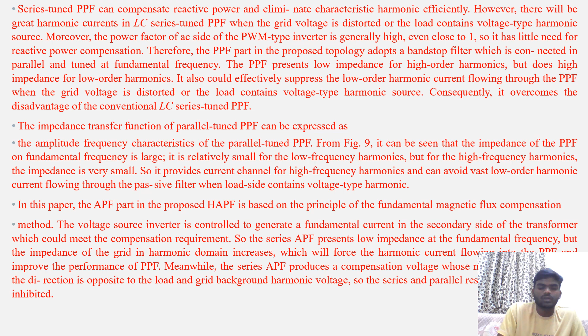When the amplitude of the current injected into the secondary winding is k times the fundamental component in the primary winding, and is opposite in phase to the primary, the fundamental main magnetic flux of the transformer is zero. At this time the leakage impedance of the primary side at the fundamental frequency is very small, assumed as R1 plus jX1, while the impedance for the nth harmonic is n times that at the fundamental frequency excitation impedance.